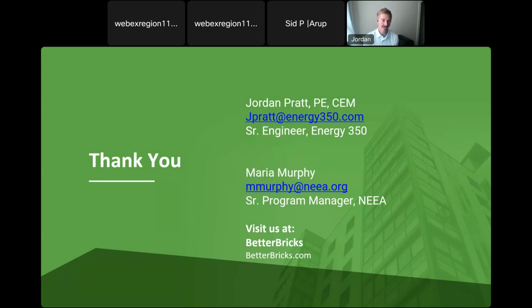And most of the literature we found has shown that when at ultra low velocities with well-placed diffusers, that limits thermal comfort issues in the winter. That's really what it comes down to, is on the winter side. So that 82% was a level with a little bit of buffer zone that allows no post conditioning and still delivering relatively room neutral air. So in warmer climates, you could certainly get away with a little bit less efficiency, but we're seeing that a lot of units are being able to deliver that with the right heat exchangers.